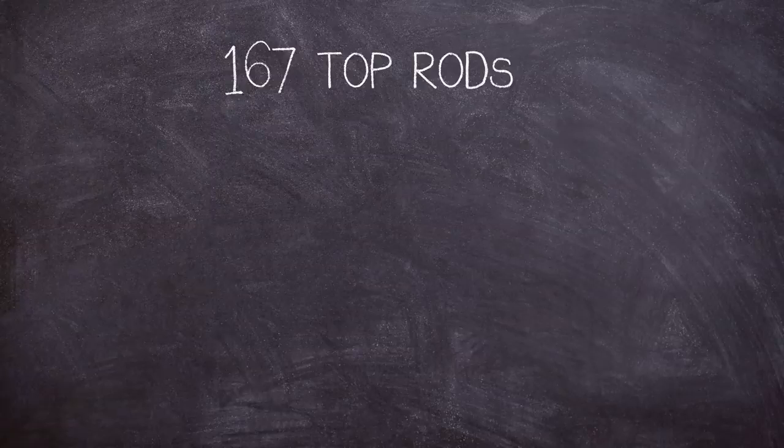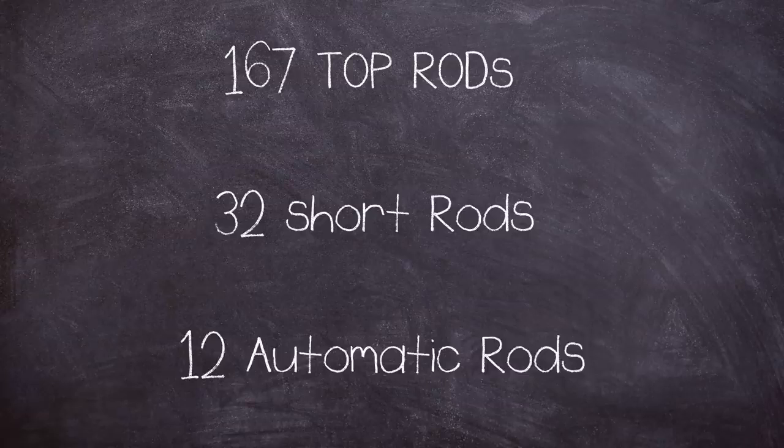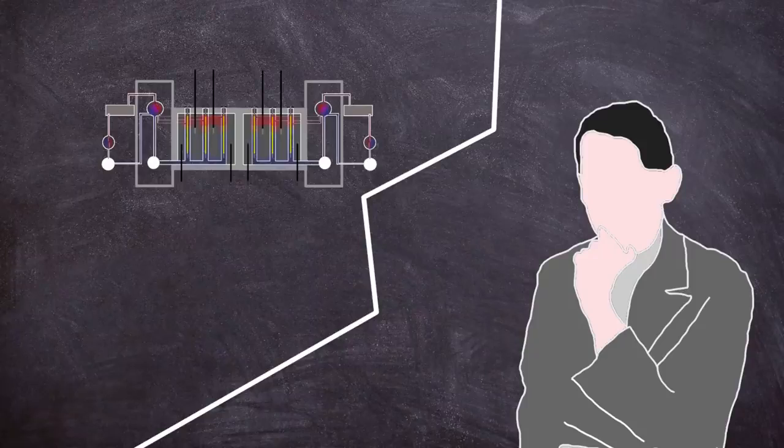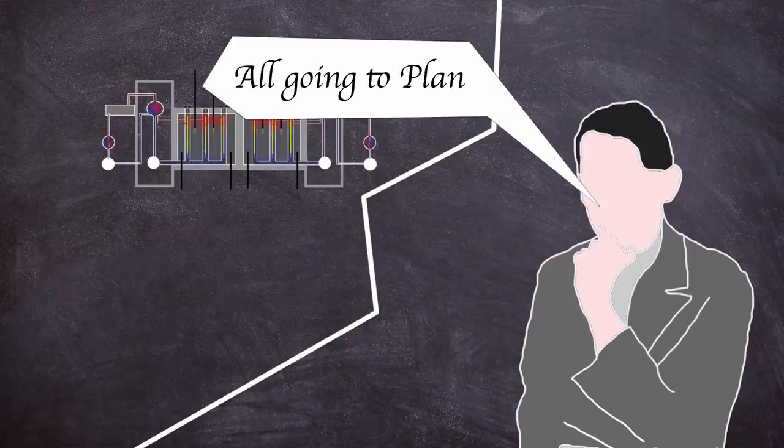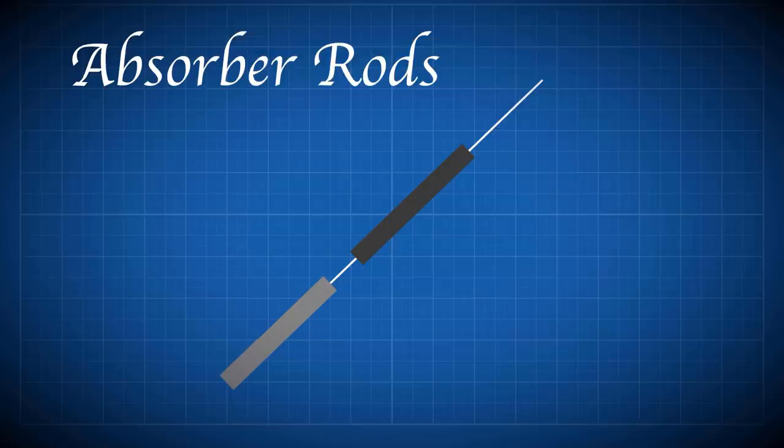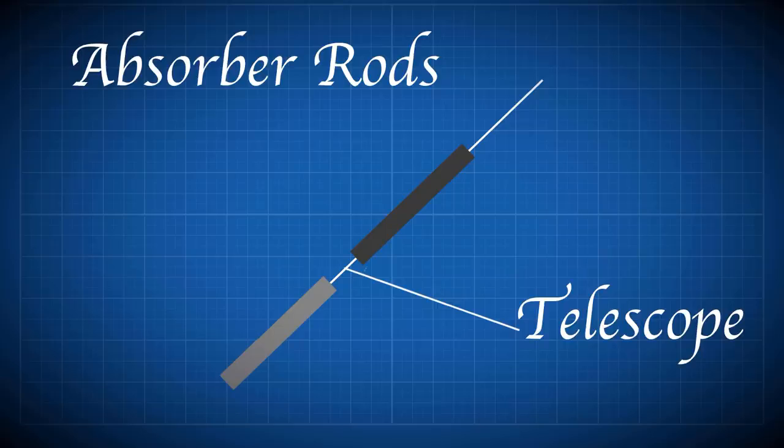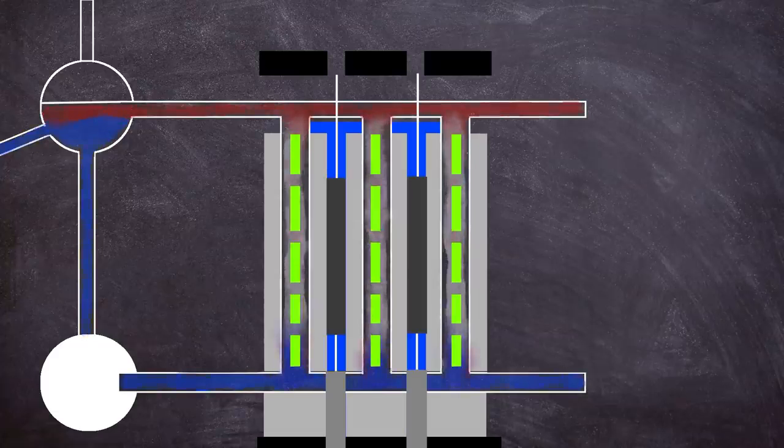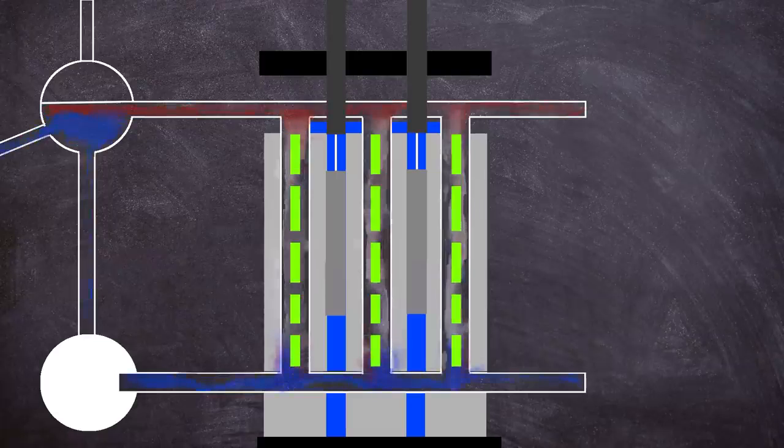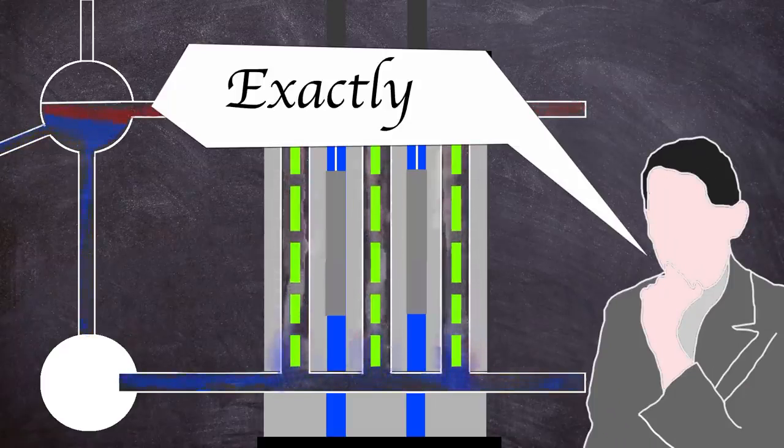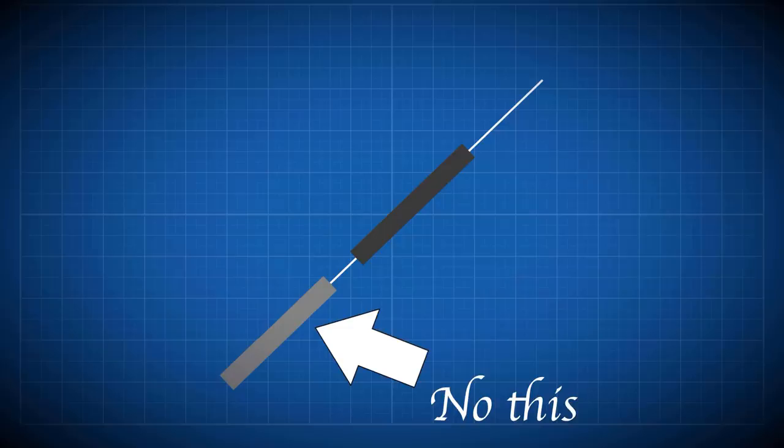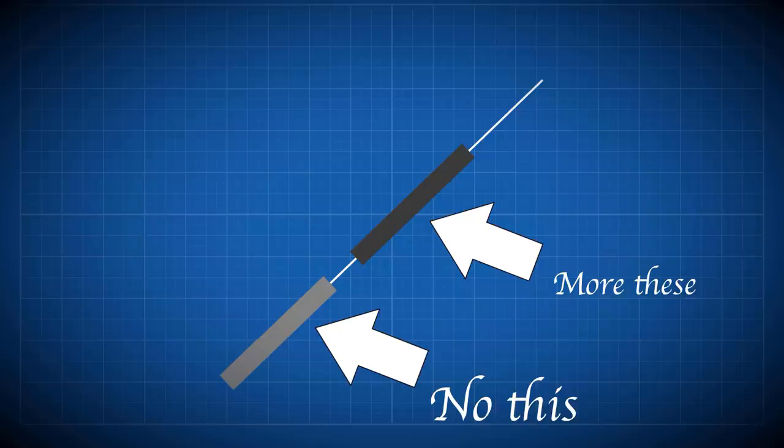There were 167 top loaded rods and 32 shortened rods loaded via the bottom and another 12 automatic controls inserted from the top. The shortened rods were used to manage axial power distribution which was necessary due to the core size to manage hot spots. The main control rods had a 4.5 meter long graphite rod termed a displacer attached to the end of the length of the control rods except for the 12 rods that were used in automatic control. The displacer connected to its rod via a telescope with a water filled space of 1.25 meters separating the displacer and absorbing rod. This was to stop water filling the space left behind by the control rod after it has left the core region which would parasitically absorb neutrons. Because removing one neutron absorber in the form of a boron control rod to be replaced by another neutron absorber albeit weaker in the form of H2O kind of defeats the point of a control rod. Thus if there was no displacer then more control rods would be needed as each one would have less of an effect on the reactivity of the core.